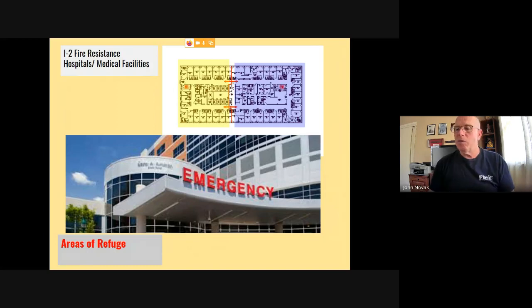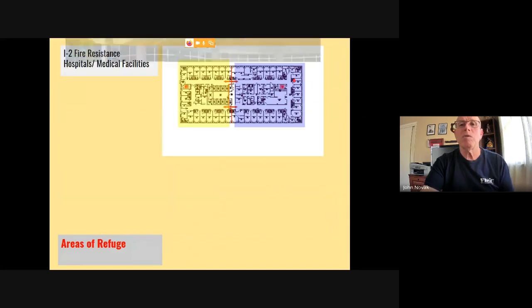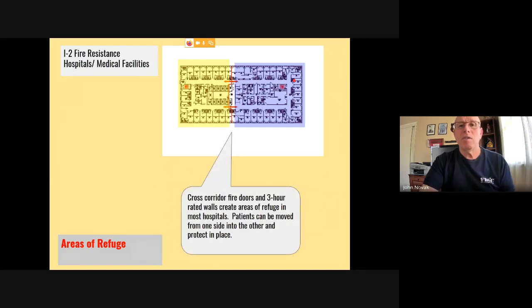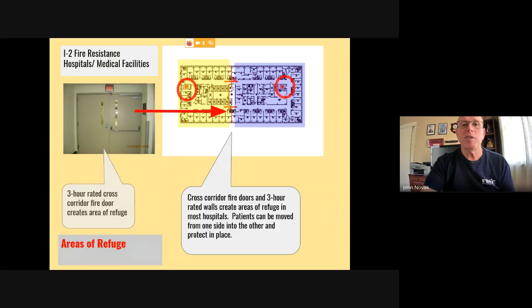So in these type of occupancies, the fire resistance rating is high because we're going to create areas of refuge. So in this illustration above here, we have a floor of a medical facility with treatment rooms, and the cross corridor fire protection basically breaks this into two fire areas. So we have a 3-hour fire separation here, and that 3-hour fire separation is maintained by the use of fire doors, right? Which automatically close on the fire alarm system.